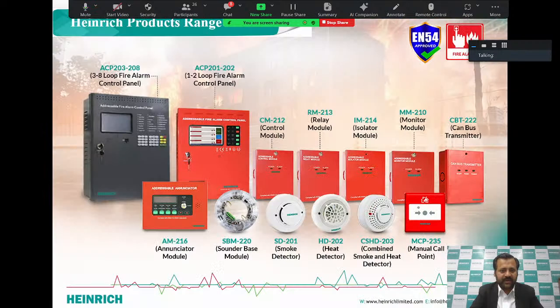This slide indicates we have an EN54 certification for our fire alarm system. Then we have two types of control panels, starting from one loop to eight loop. We have an LCD screen on that. We have repeater panels. We have a sounder base. We have smoke detectors, heat detectors, multi-criteria detectors, MCPs. Then we have control modules, relay modules, and isolator modules to get other systems integrated with the fire alarm system as well.